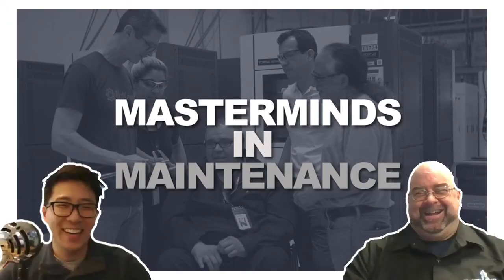So when do you use a current signature analysis versus a vibration analysis? I will let you in on a little secret. For a long time, the discussion within the industry is, whatever we do, don't say we can detect mechanical issues. Well, why not? Well, because we might get the vibration guys angry. Well, who cares? I'm a vibration guy. I'm not angry because I can go with an electrical signature analysis.